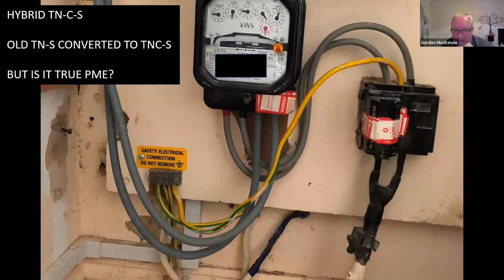No, correct. The interesting thing, I was looking at the cable there, Paul, is that an underground service that's coming in that image? Yes, it is. So we're obliged as a DNO to comply with ESQCR, and the sheath of that cable must be connected to earth. So the distribution of that cable is SNE constructed TNS, but it looks like somebody's decided, for whatever reason, probably because the earth has failed at some point on that, to dip it in beside the neutral and effectively convert that. And that's what we saw in a lot of our DNOs.